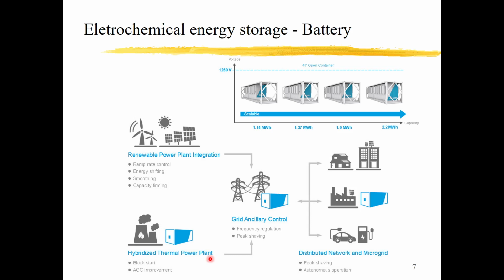Okay, usually the power inside the plant is supplied by diesel generators. They need diesel generators to supply the power. This is called a black start, because you want to start the power plant but you need power, and the power has to come from another source. Now we can use the energy storage to serve as a power source.